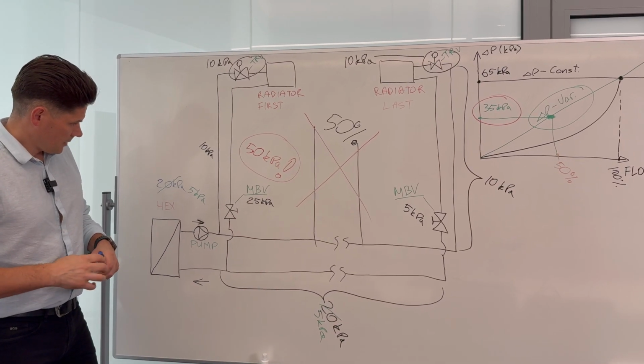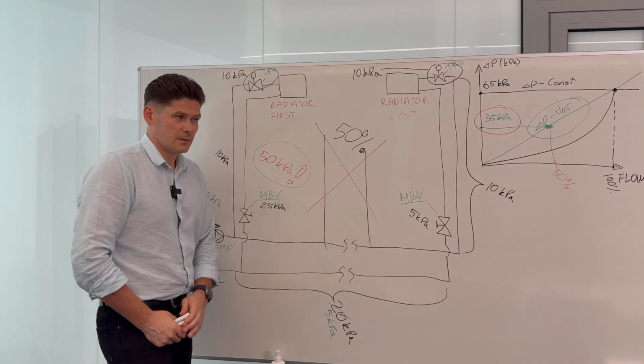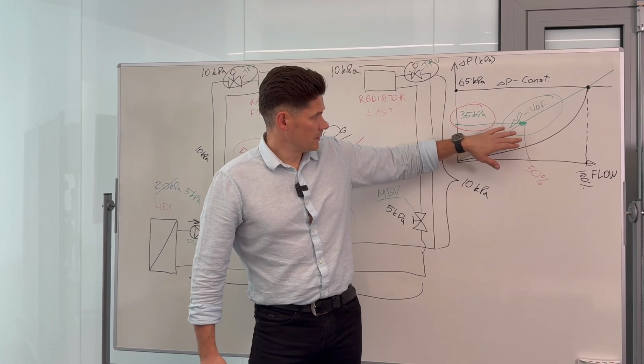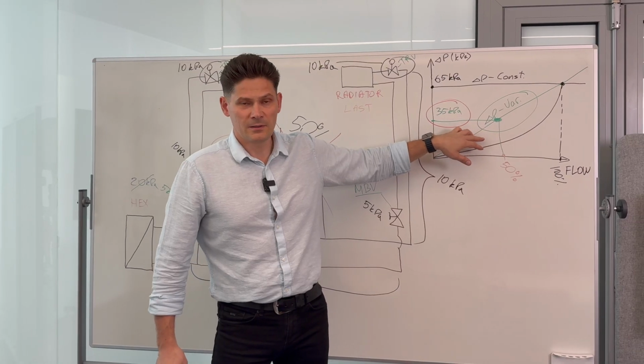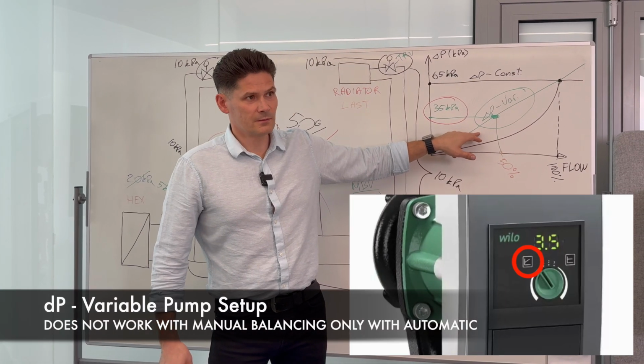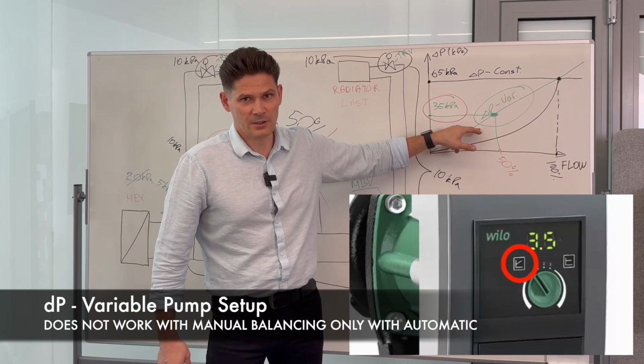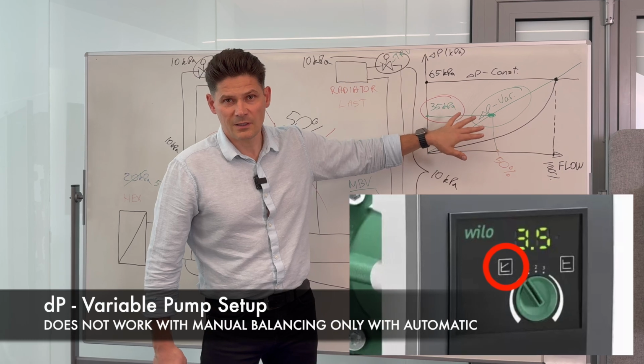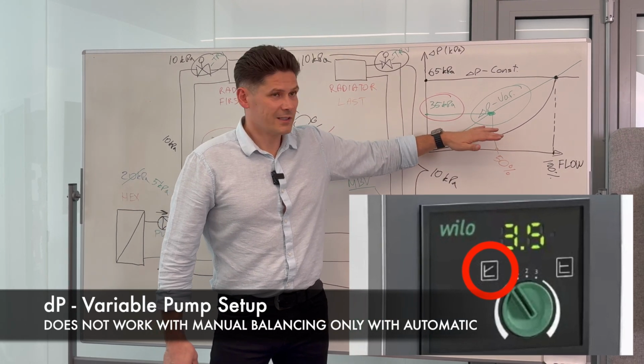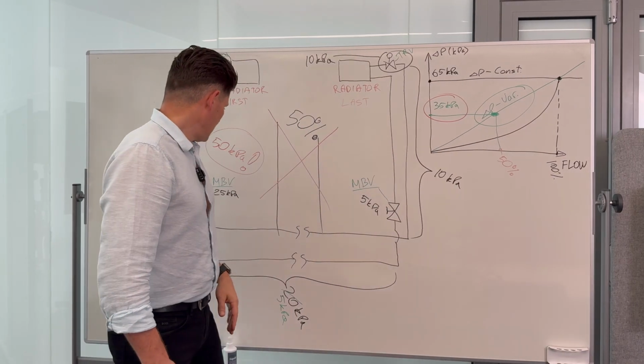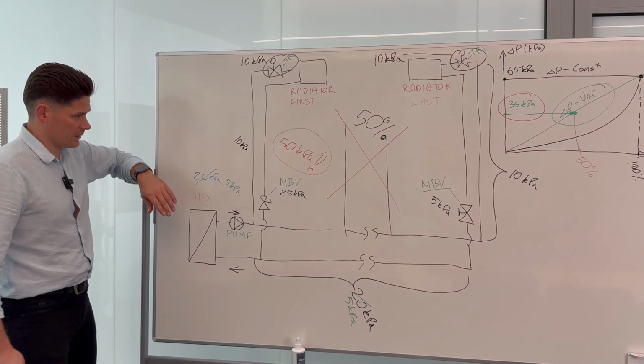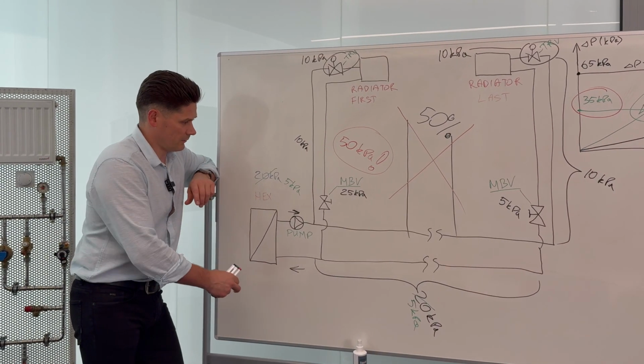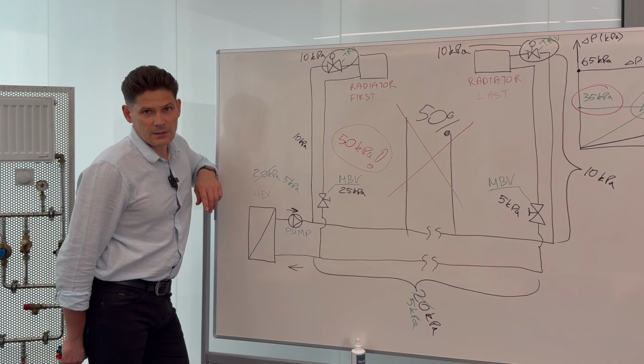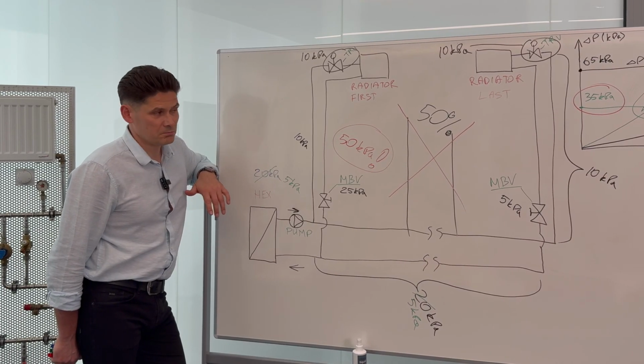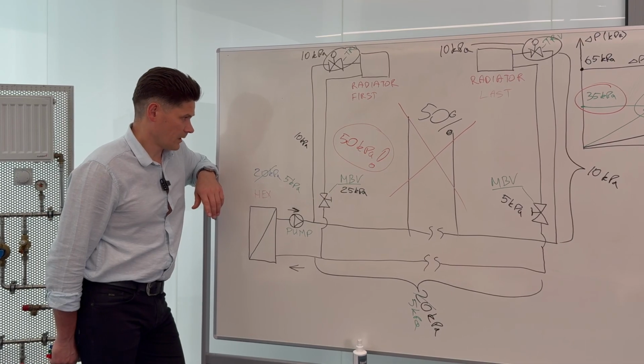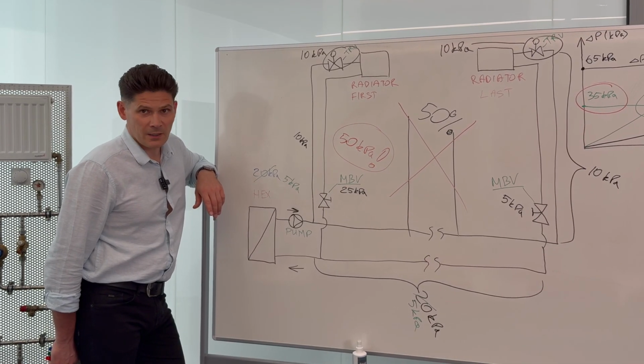So this means in a system with a modern circulation pump, where we have a delta P variable setup, this type of circulation pump regulation is very efficient. It is the most efficient these days. So having this setup at partial load, when half of the risers close, I will have a shortage of flow into the first risers. So this is what happens in systems with manual balancing valves.